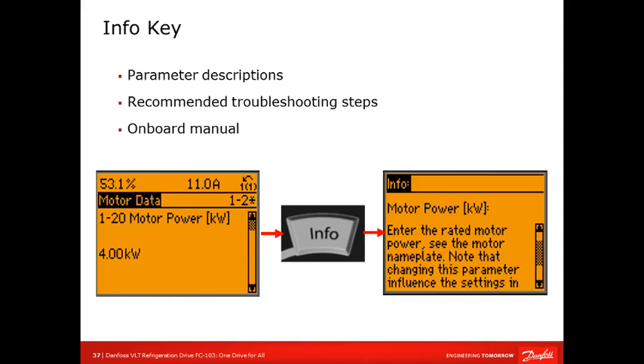This goes back to what I was saying earlier about the info key. Not only are you getting a description of the parameter, there's the onboard manual, so you can actually read a description telling the operator. So it's a great setup. And what's nice too is that with our keypad, you can remove it even if it's running and plug it into another Danfoss VFD. So again, easy to work with. The advantage for us is the same interface, whether you're using a 2 horsepower or a 300 horsepower drive. The good news is you don't have to learn a whole new parameter structure or layout. Internally, we know that if you know one of our VFDs, you know them all.